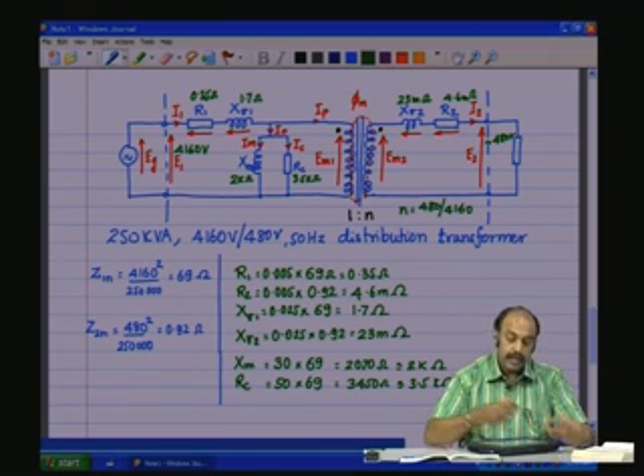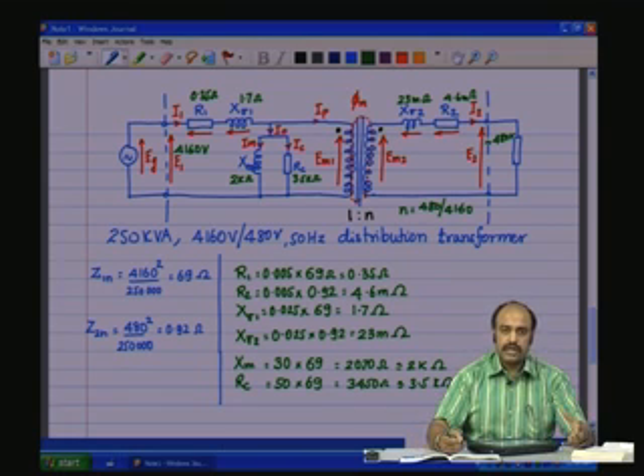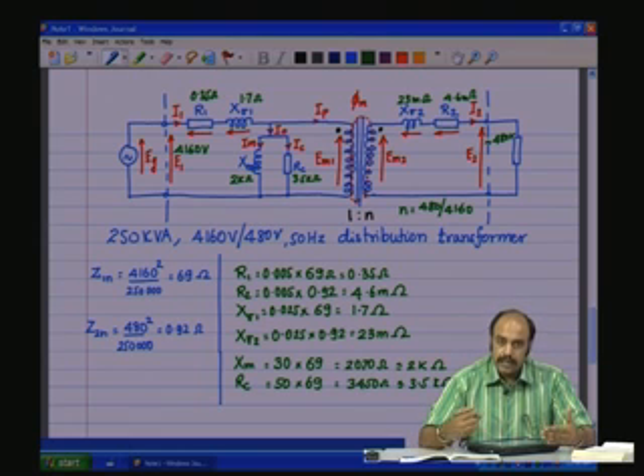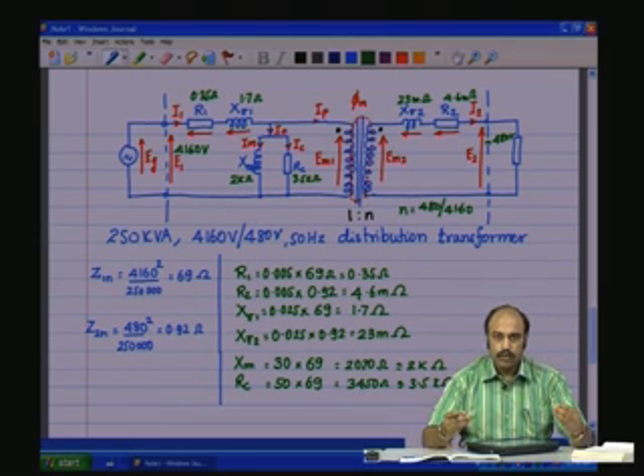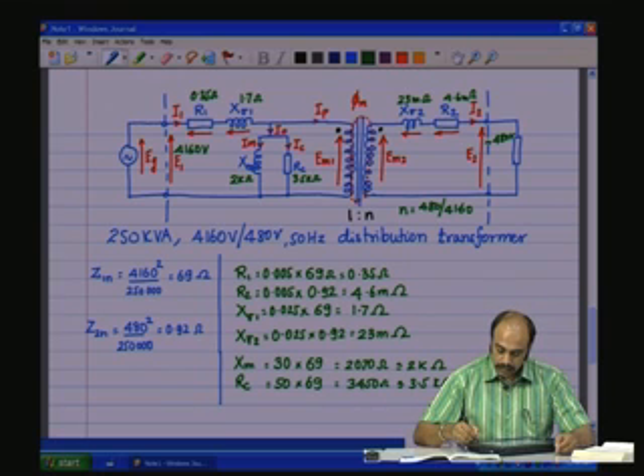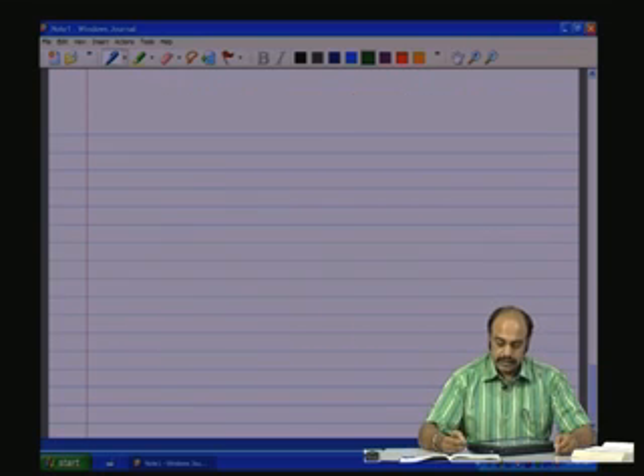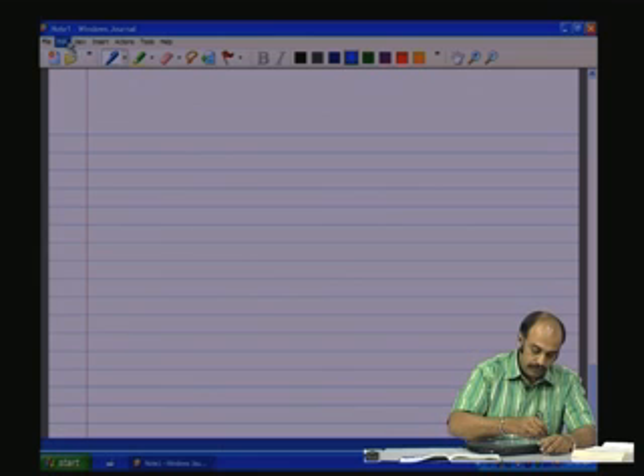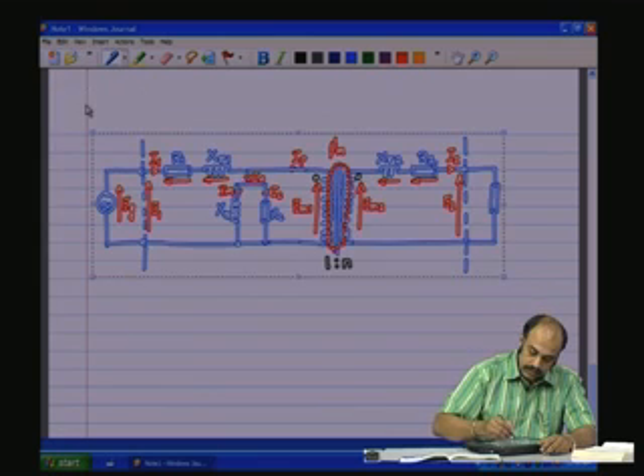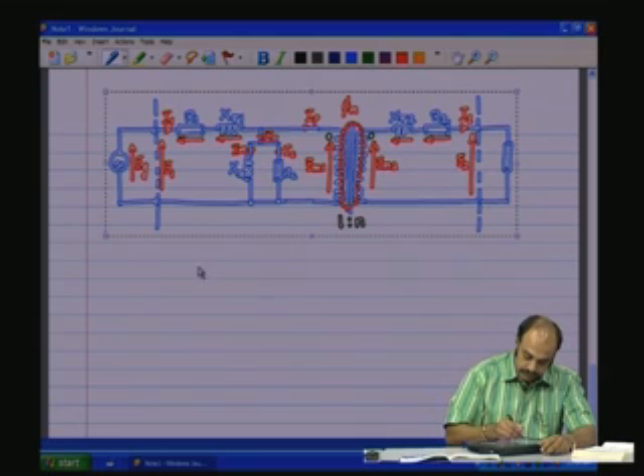So, given the power rating of the transformer, looking at the table of per unit values, one can obtain the order of values of the various resistances and the reactances of the transformer, and this will give you a comparison between various transformers from various manufacturers of the same rating. Now, the next point we would like to discuss is the equivalent circuit itself.